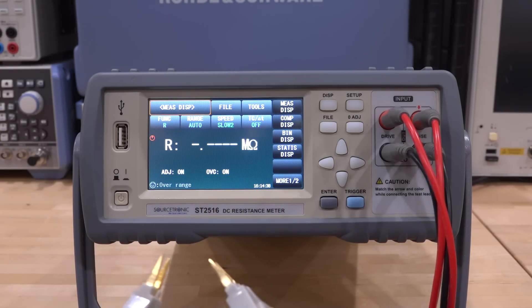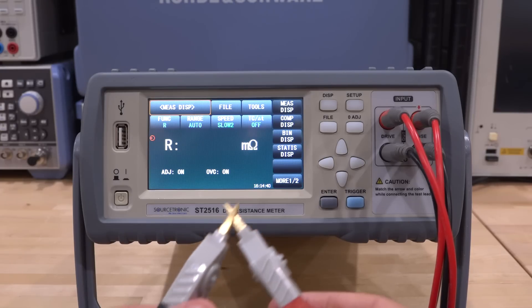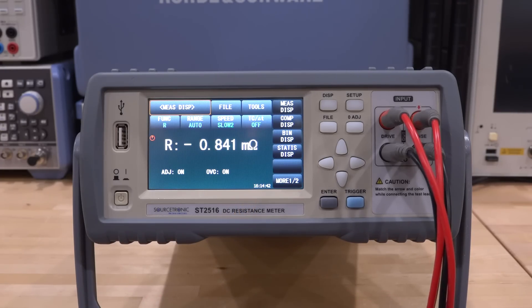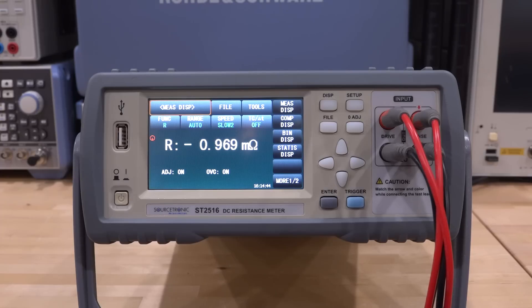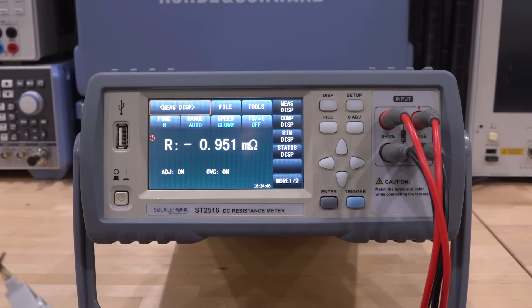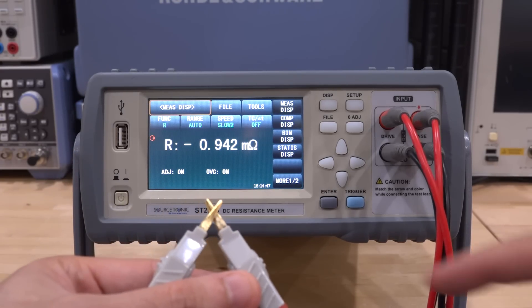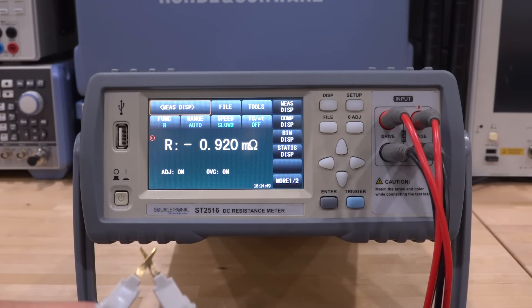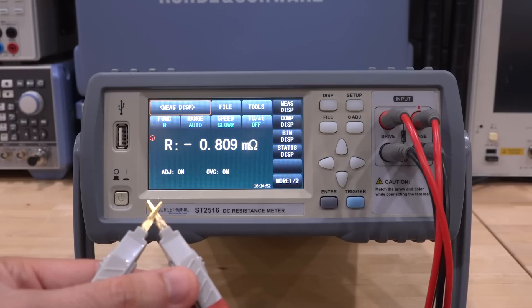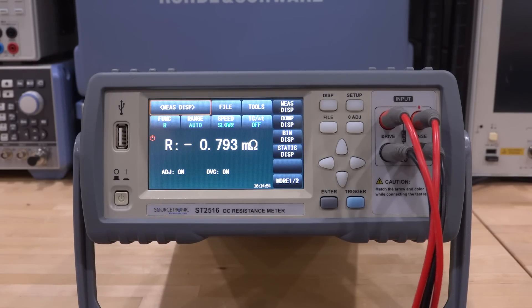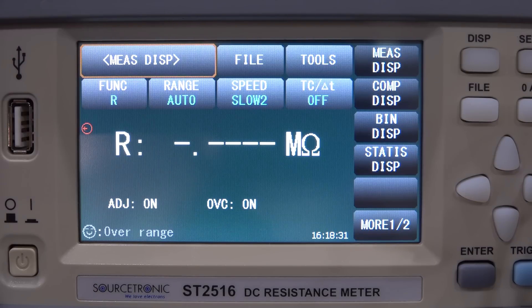We got ourselves some Kelvin clips plugged into the instrument like so, so we should be able to connect this to something. Now the first thing to do is to zero this instrument by connecting everything together. I'll do that off screen to just have a zero adjustment which will get rid of basically all the internal resistances as well as the thermoelectric effect. We'll talk about that in a second because that's an interesting thing. I'm going to set it up and see how that works but first let's measure some resistances.